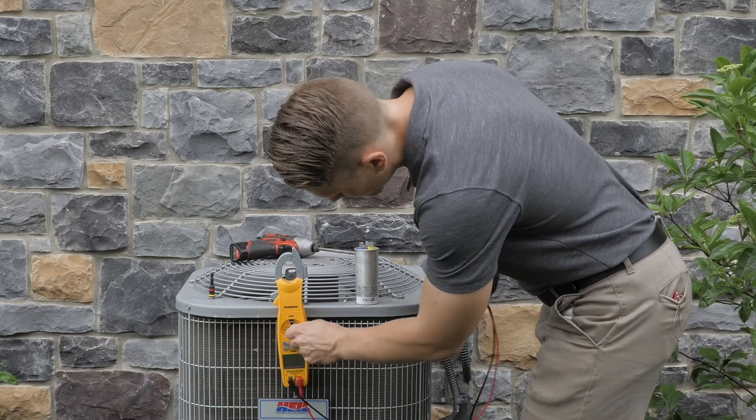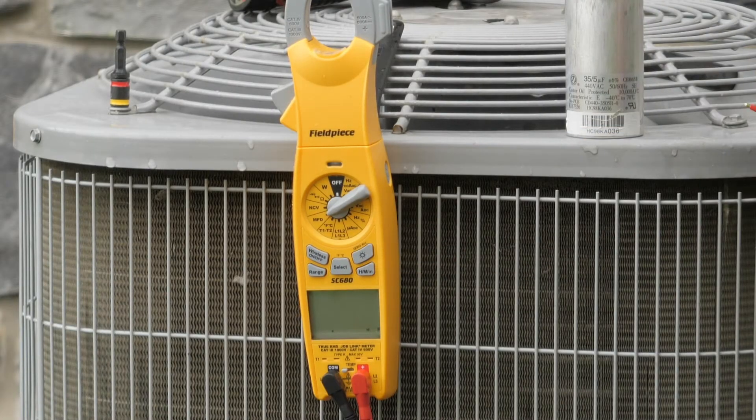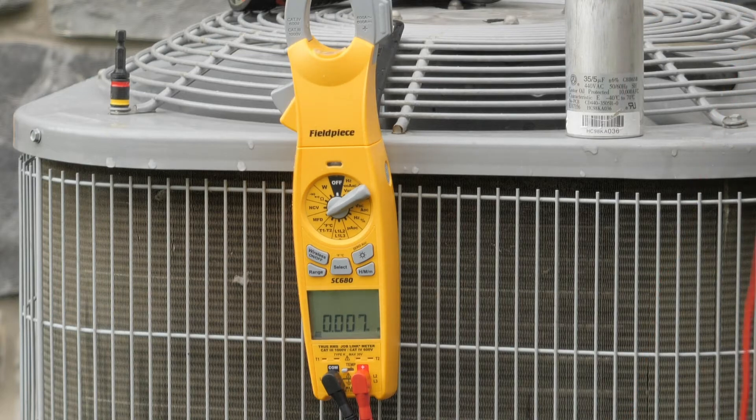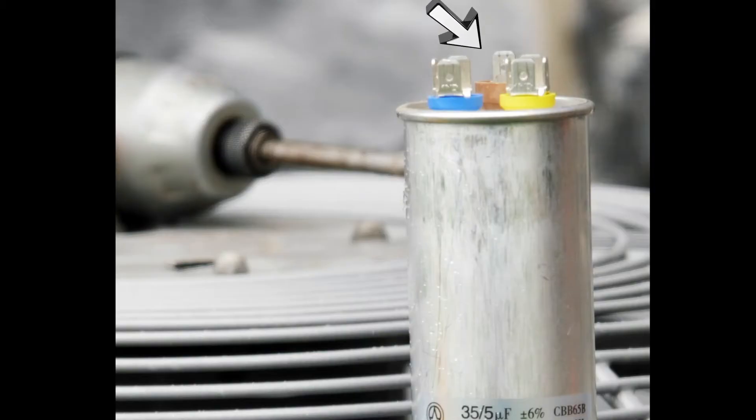Pull out your multimeter and set it to MFD for microfarad or UF for microfarad. You're going to have three terminals on the top of the capacitor: C, F, and H. These stand for C is common, F is fan, and H is Herm, which is the compressor.